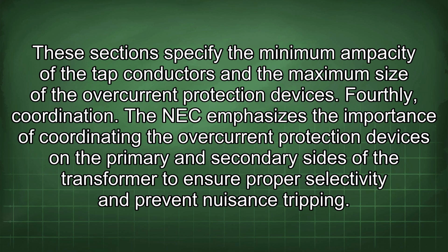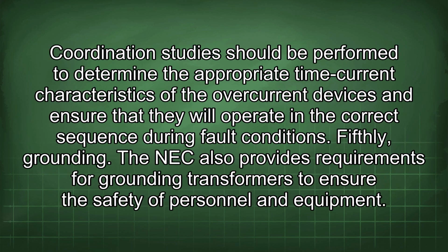Fourthly, coordination. The NEC emphasizes the importance of coordinating the overcurrent protection devices on the primary and secondary sides of the transformer to ensure proper selectivity and prevent nuisance tripping. Coordination studies should be performed to determine the appropriate time-current characteristics of the overcurrent devices and ensure that they will operate in the correct sequence during fault conditions.